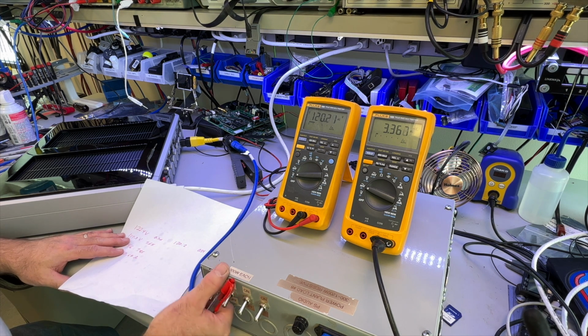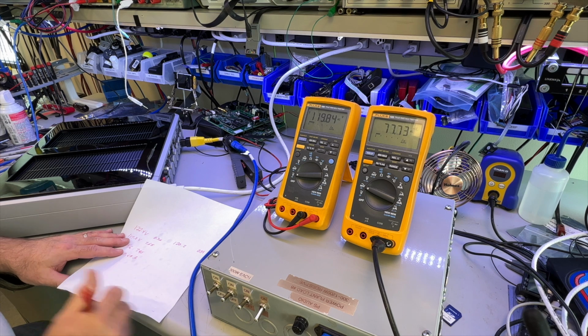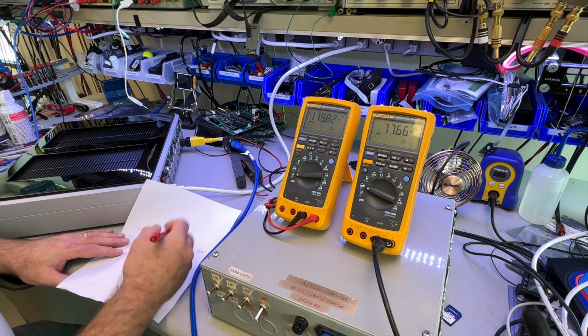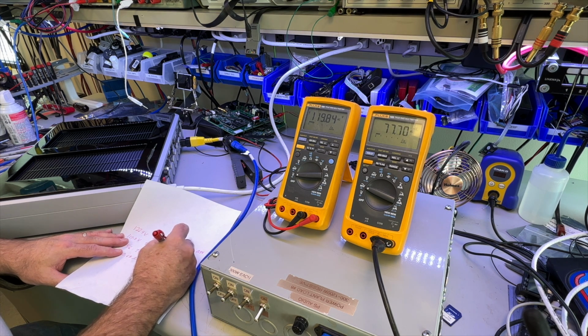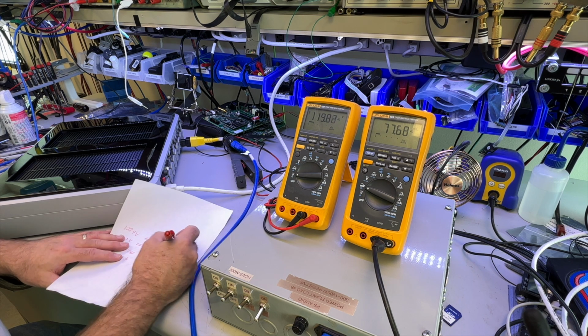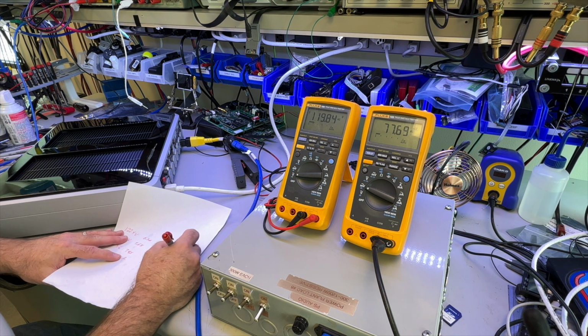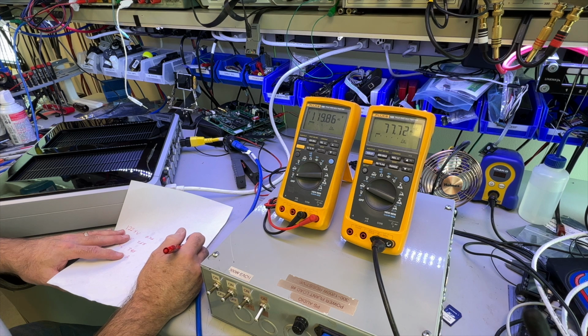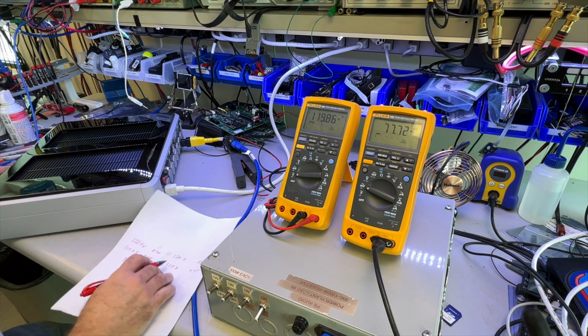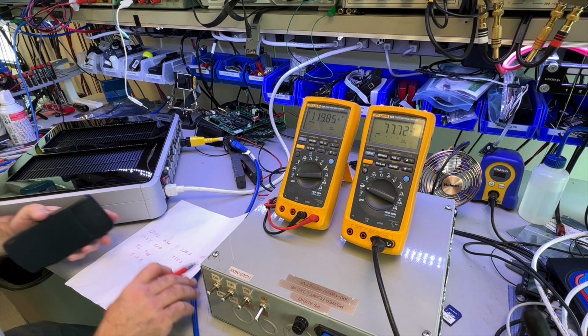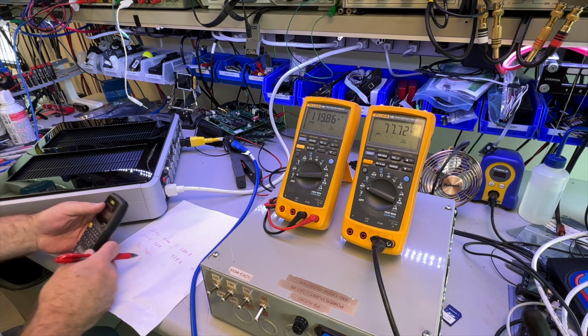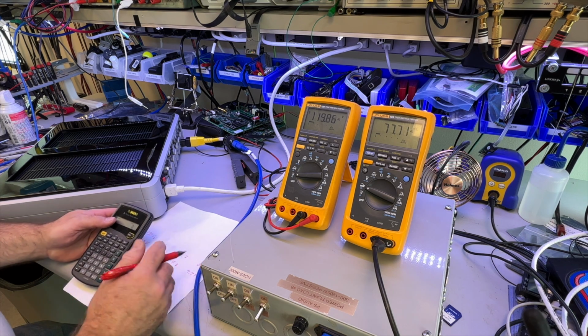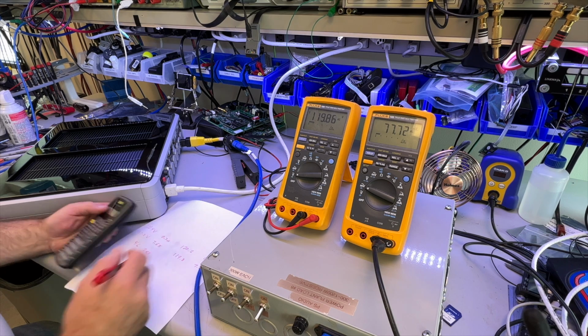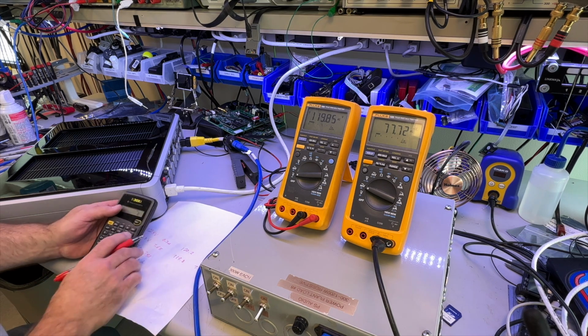So I'm going to turn on the same 3 resistive loads, and we can see the voltage dropped just a tiny bit, to 119.8. So we went from 120 to 119.8 — that's a little less than 200 millivolts. We dropped maybe 300 or 400 millivolts, whereas it was slightly above 120 before, as opposed to multiple volts, which is what dropped when we were right at the wall — we were 4.6 volts down before.